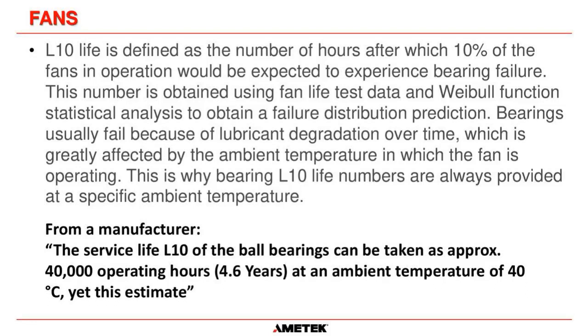The way fan manufacturers list their fan life is once again in hours, but they use the L10 life. And that is defined as the number of hours at which they expect 10% of the fans in operation would experience a bearing failure. And that number is obtained using test data and this fancy Weibull function statistical analysis. Never heard of that before, but that's what the fan manufacturers use. And basically it says bearings usually fail because of lubricant degradation over time, which is greatly affected by the ambient temperature.